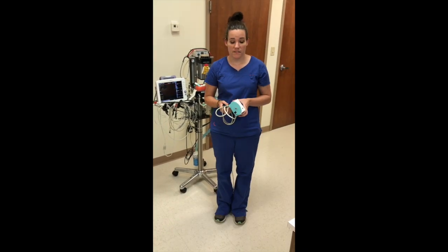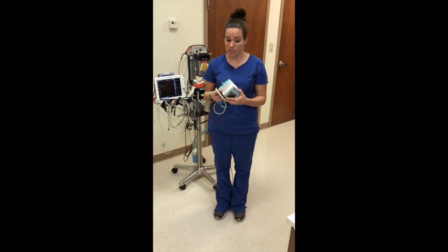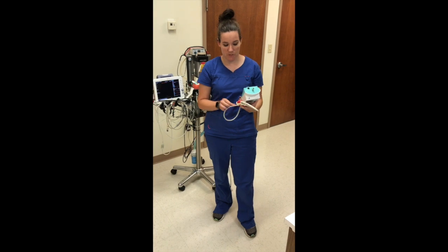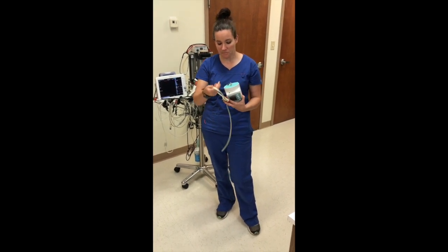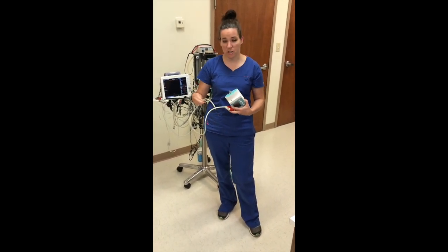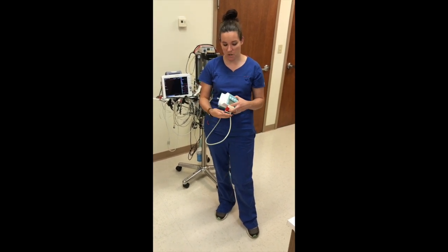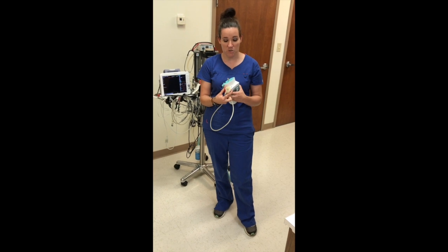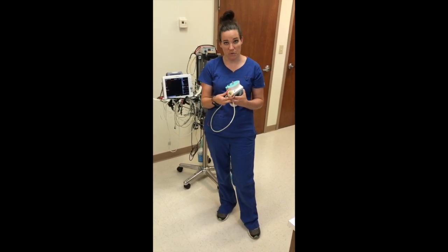This is our blood pressure monitor. This is an HDO unit. It comes with several different cuff sizes. What we end up doing with this is we put this cuff around preferably a tail. If not a tail, we put it around a front leg. We want it to be a snug fit but not too tight. If it's too loose, it also won't read as well either.